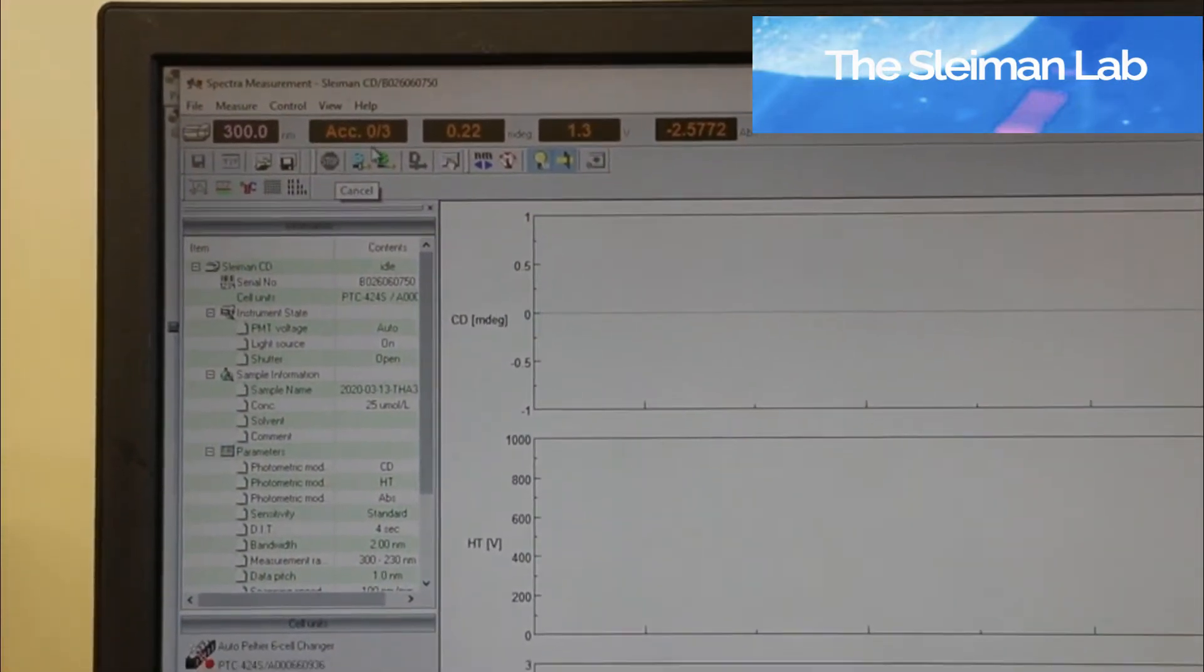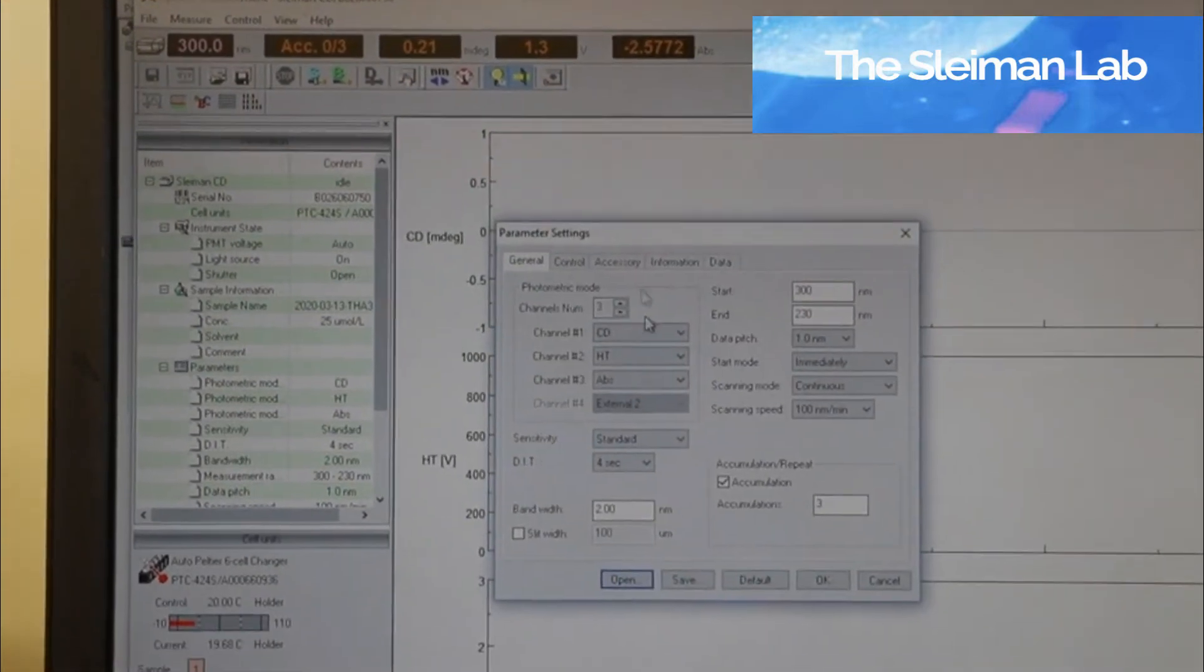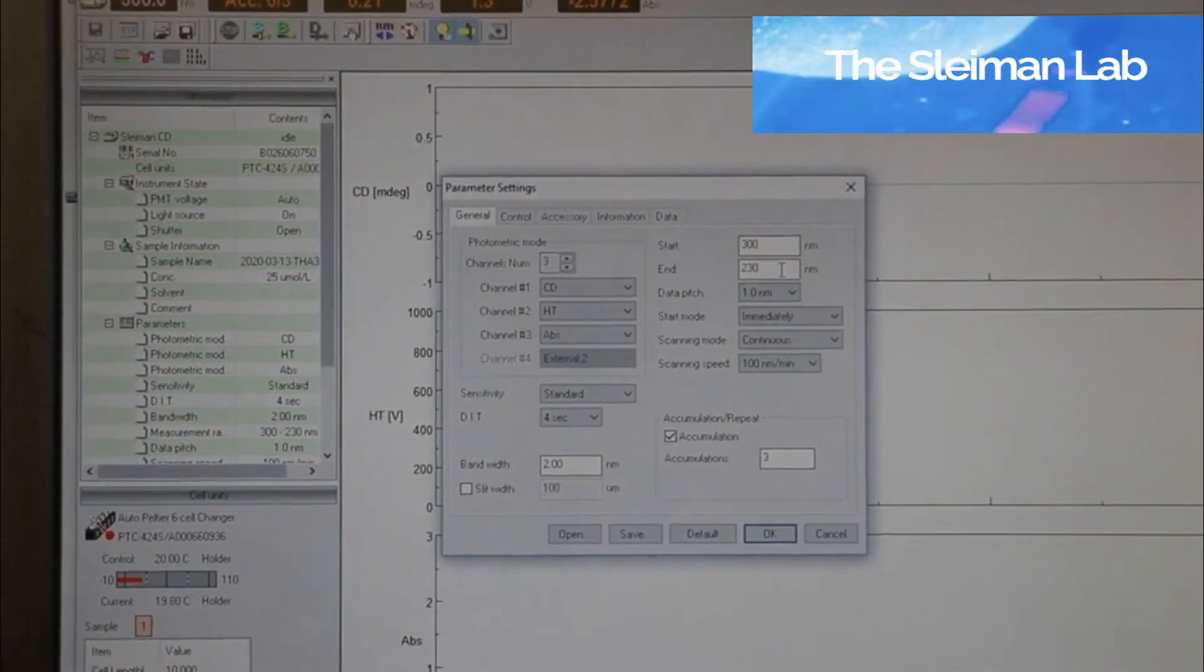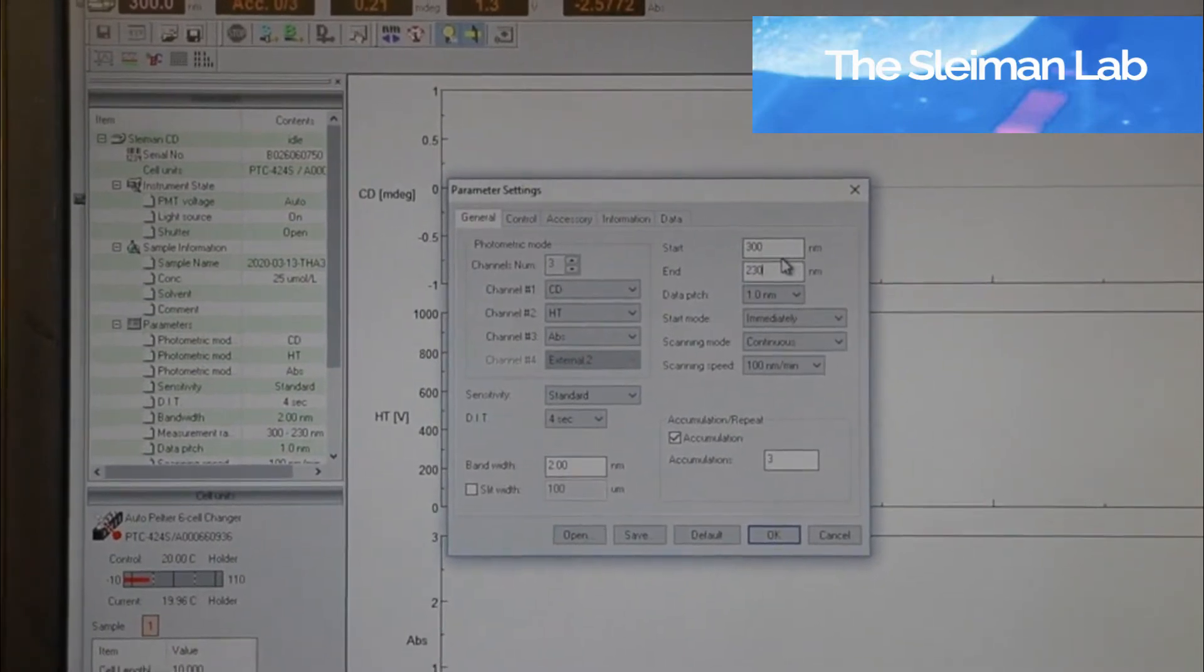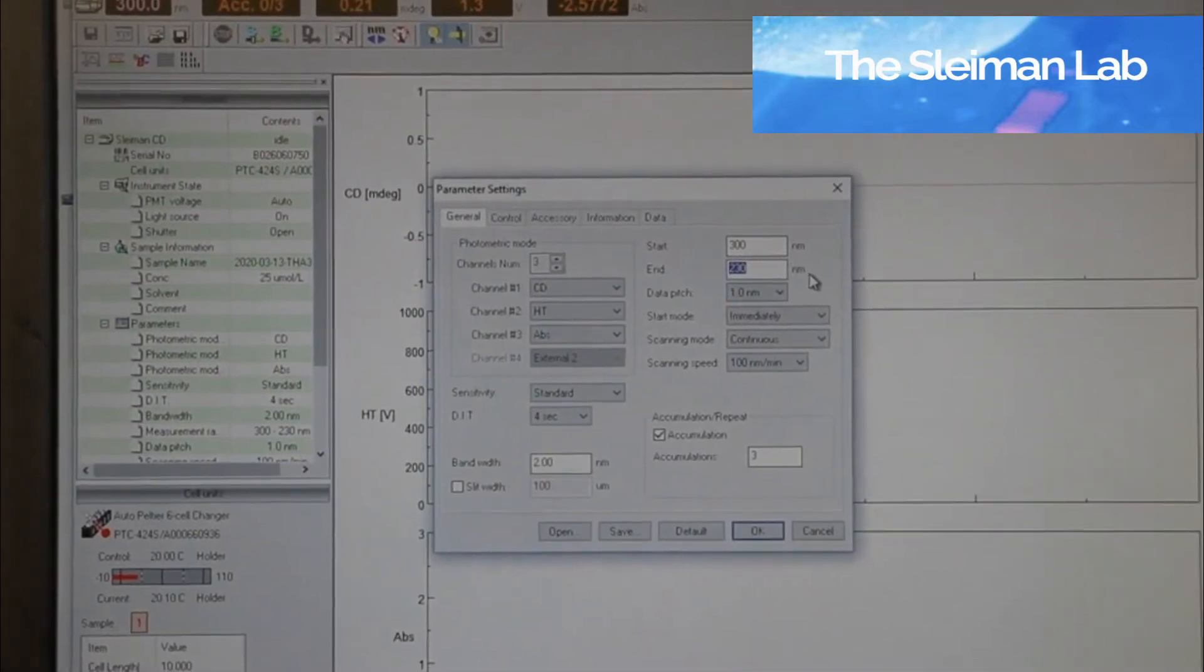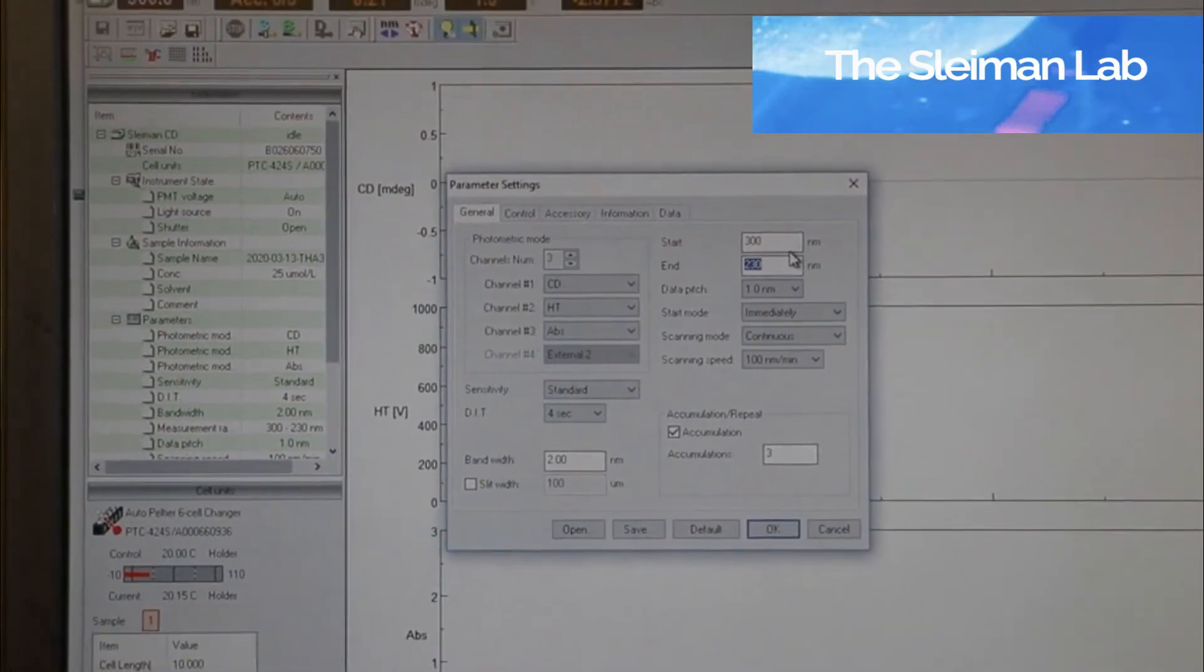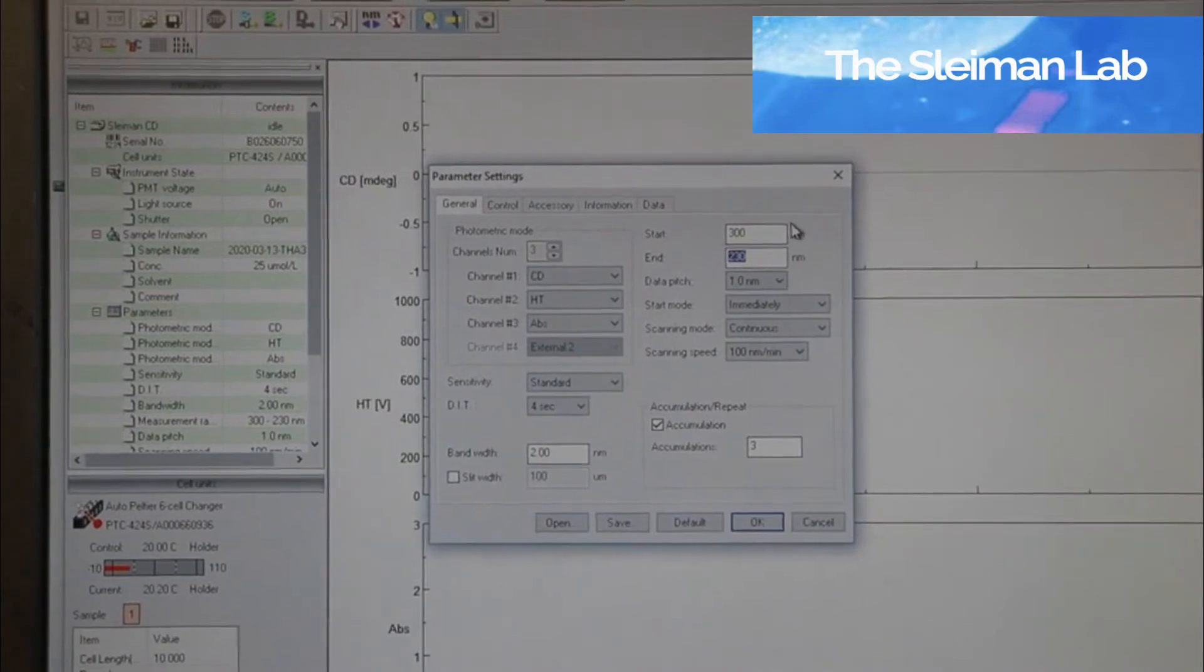Next step is going into this parameters window, which allows you to define the parameters of your experiment. These general parameters are what scans you wish to undertake and what wavelengths you wish to undertake as scans. The lower end of your wavelengths will depend on the lamp you have, and also if you have an attached nitrogen or argon tank to purge the system if you have wavelengths and lamps that produce ozone.